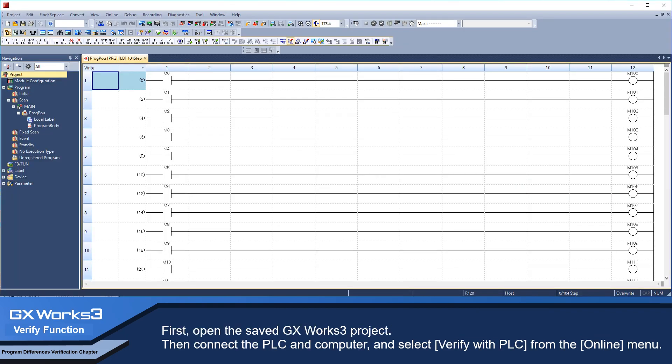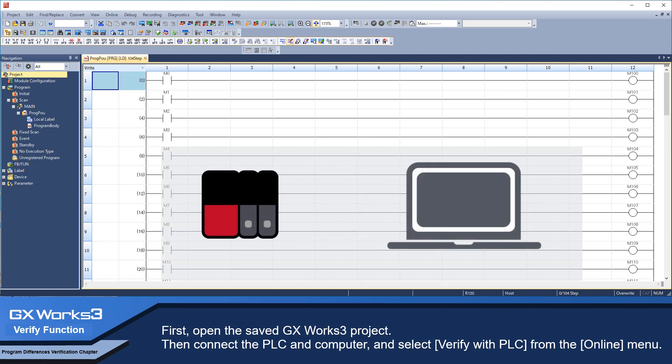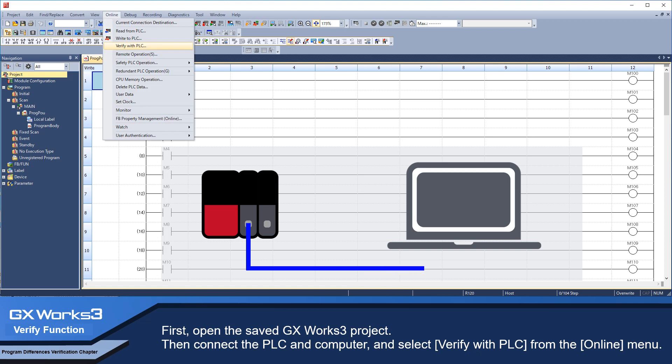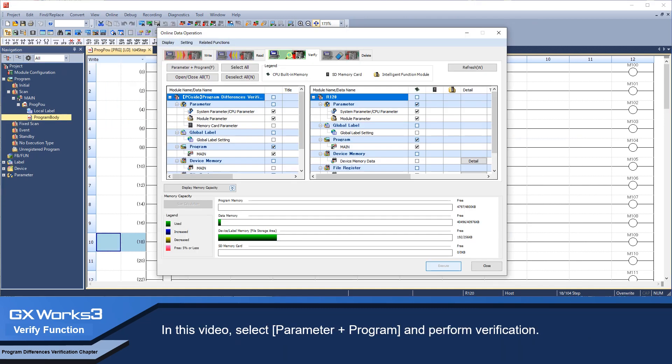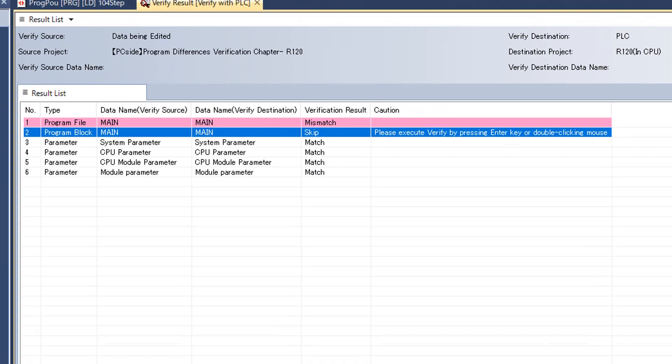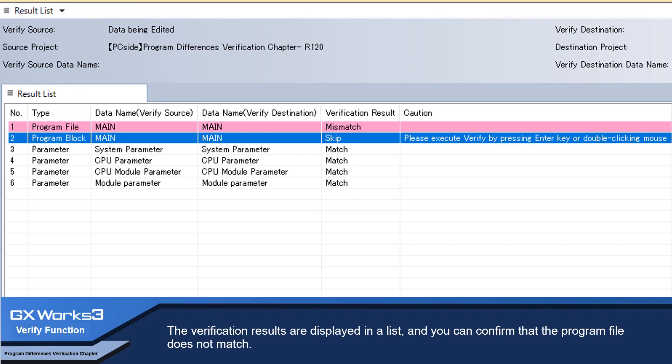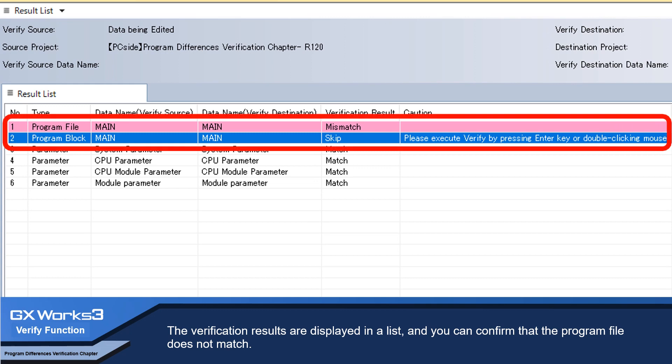First, open the saved GX Works 3 project, then connect the PLC and computer and select Verify with PLC from the Online menu. In this video, select Parameter plus Program and perform verification. The verification results are displayed in a list and you can confirm that the program file does not match.